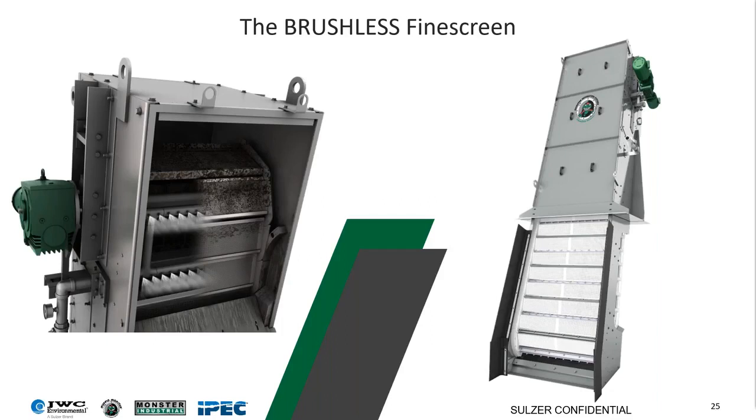But how is it that your screen doesn't require a brush, you ask? So the brushless screen has a very specific application. Obviously, there are owners who really don't want the brush at any cost. So this is our target client here. However, because the brush is removed, we add a secondary spray system to take its place, and water consumption is higher, and that can be an important consideration, obviously.